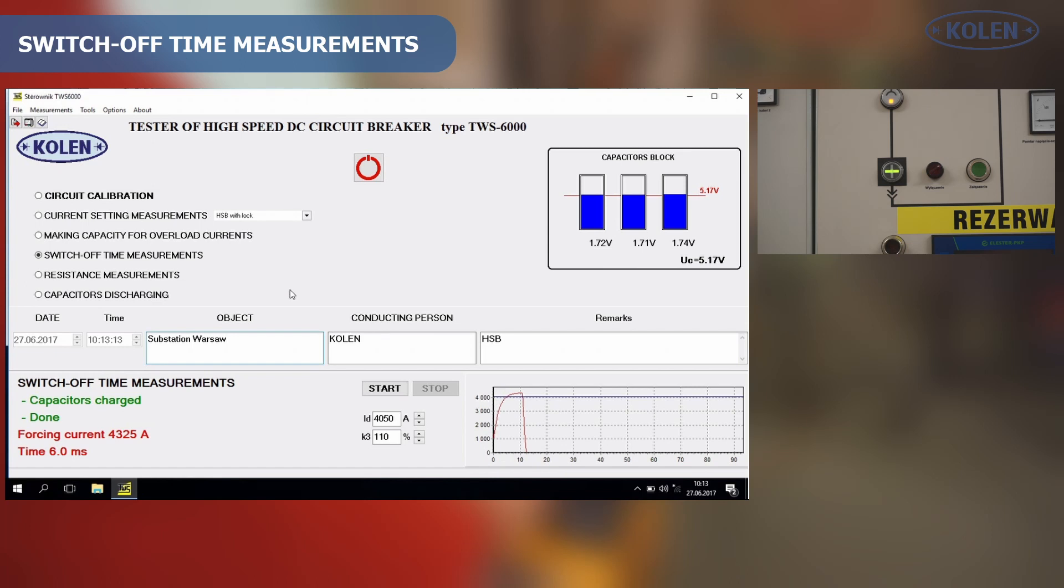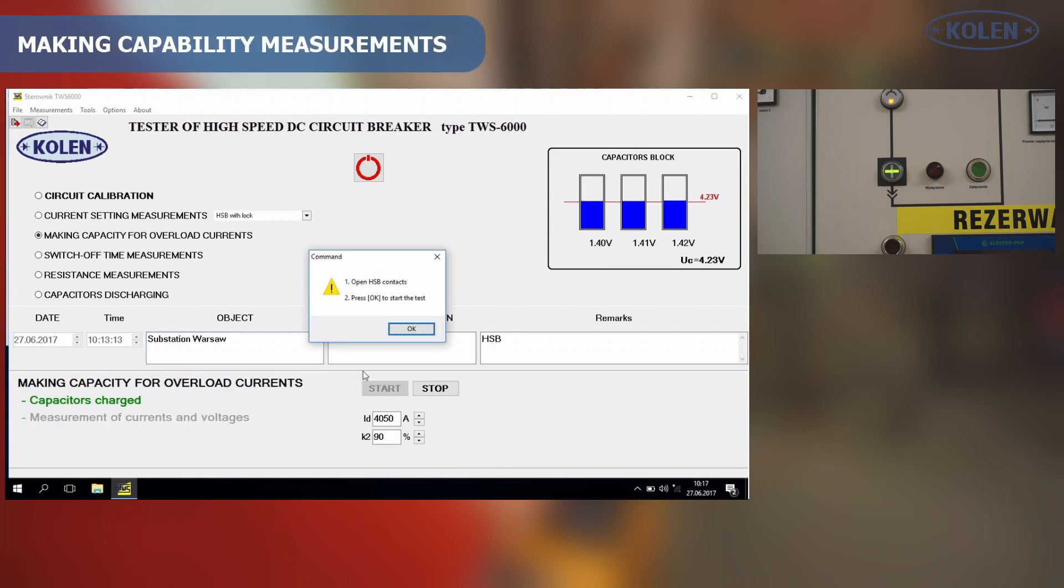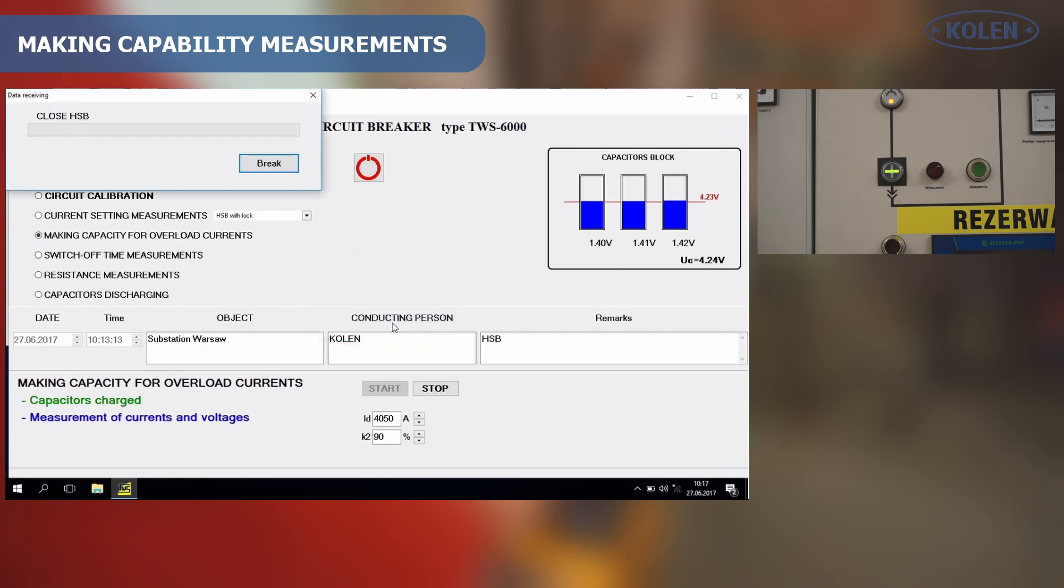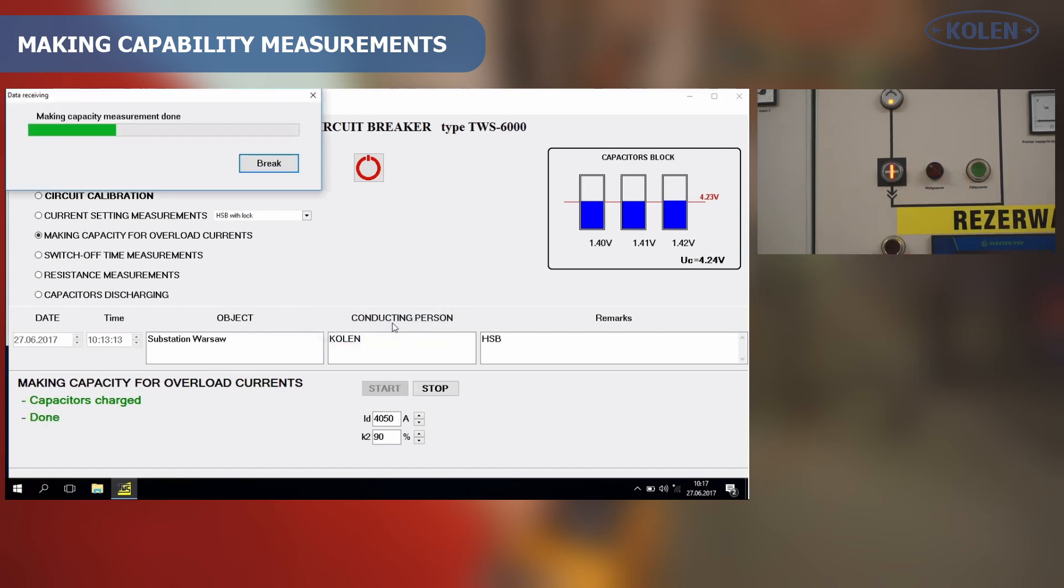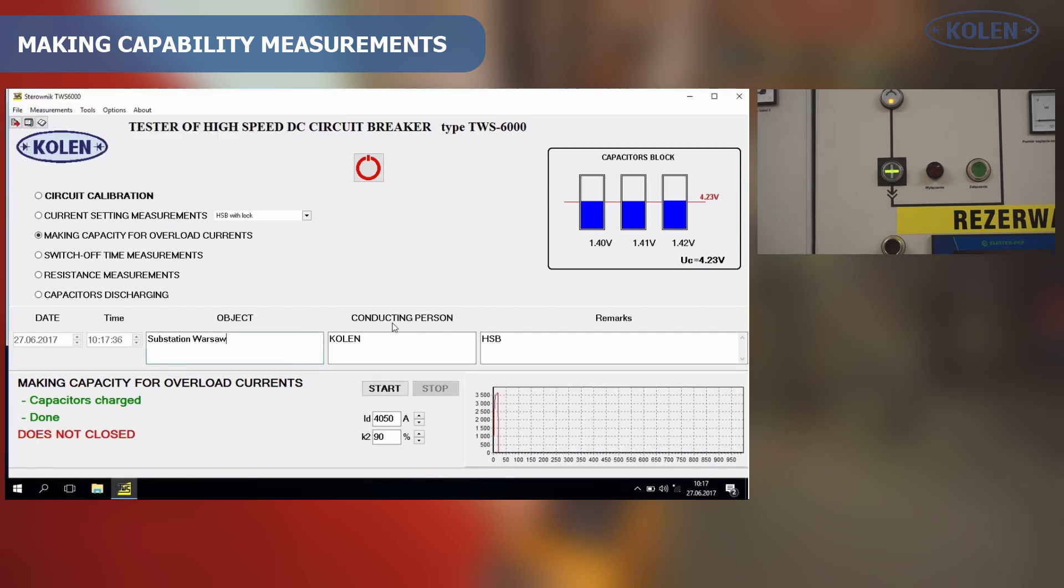The measurement of HSB making capability under load condition is performed with the probing current value adjusted according to the manufacturer specification. This test passes for a given value of probing current when HSB's main contact closes permanently.